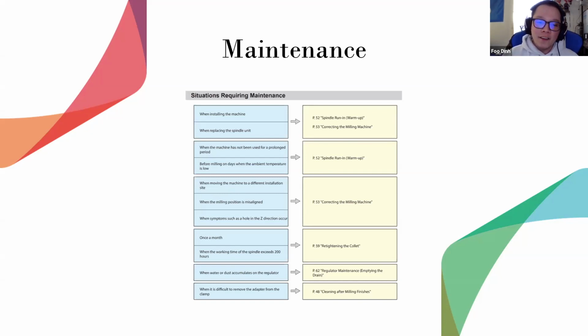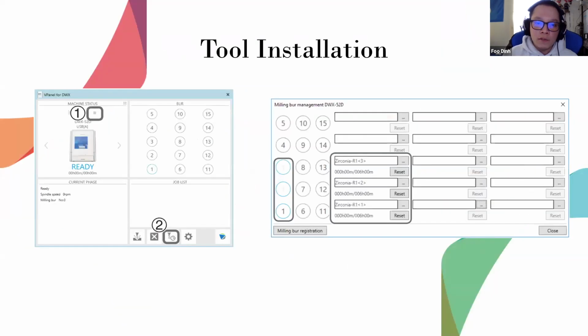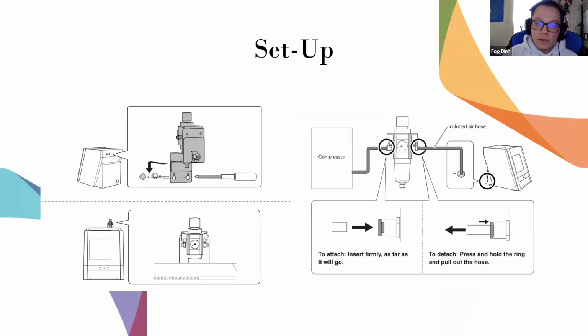Okay. All right. Now, water and dust accumulation. Where that comes from is really the air regulator that's on the back of the mill. I want to say at least once a month while you're doing the calibration and the collet tightening, you just want to crack open the small screw on the bottom of the regulator. Right here on the bottom of the regulator.